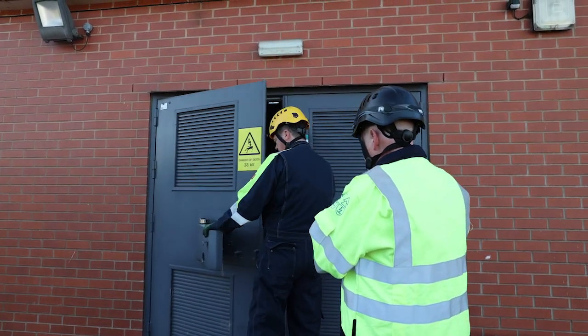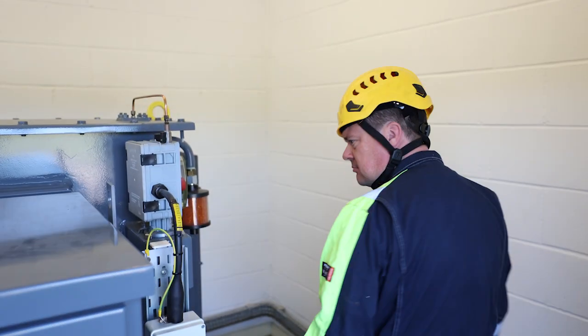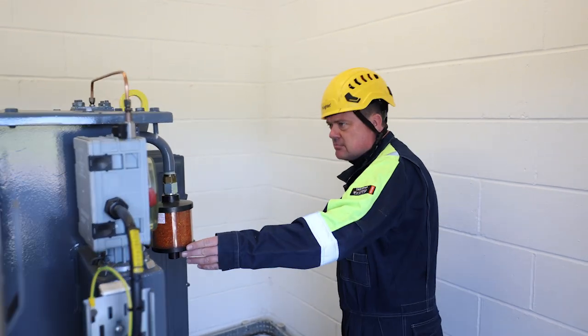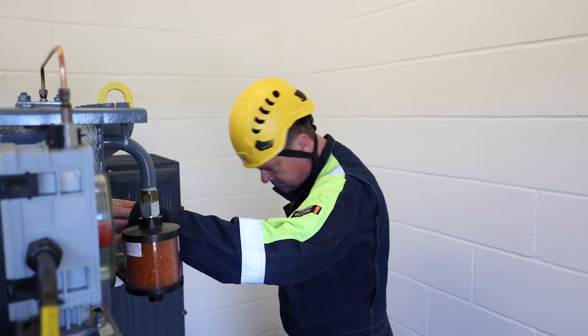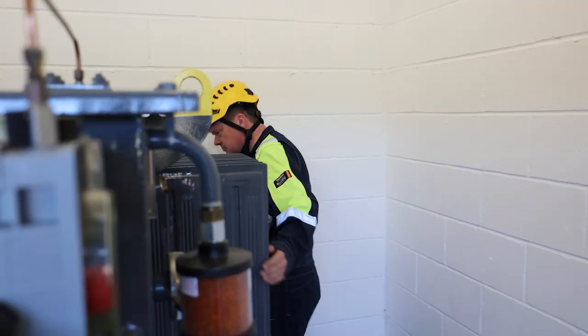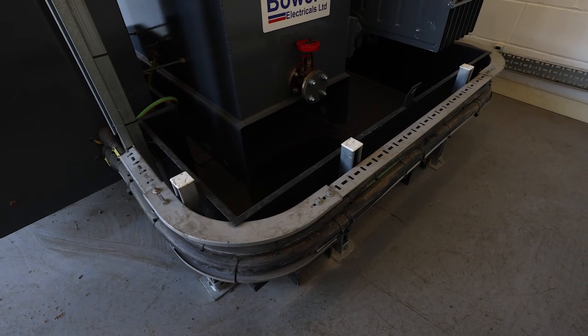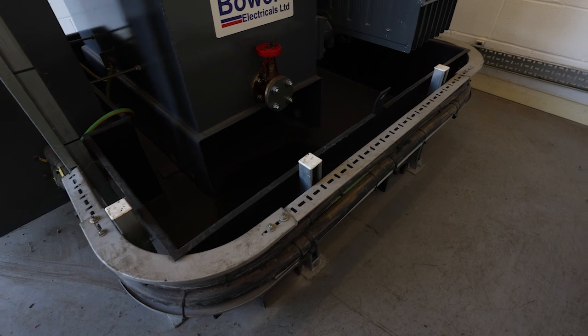And that's normal? Yes, but if you're unsure, get someone else to listen to it, perhaps high voltage colleagues. And you should do a visual check on the transformer to see if there are any areas of distress or deformation. And you need to check for leaks as well. Leaks? Yeah, if the transformer is oil filled, then the oil is the insulator. If this has leaked out from the transformer, it could be in a dangerous state.